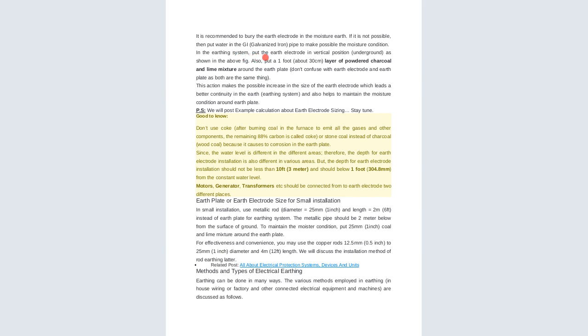So in the earthing system, put an earth electrode in a vertical position underground, as shown in the figure above, and put a 1 foot, that is a 30 centimeter, layer of powdered charcoal and lime mixture around the earth plate. Do not confuse earth electrode and earth plate, as both are the same thing. This action increases the effective size of the earth electrode, which gives better continuity in the earthing system, and also helps in maintaining the moisture condition.